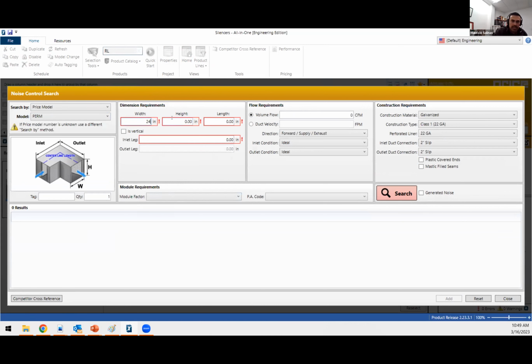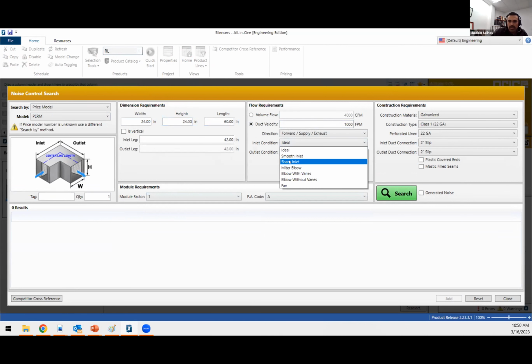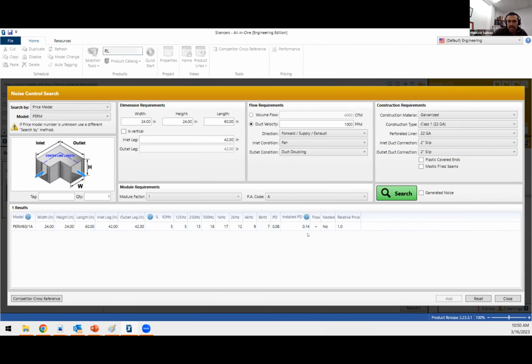So when you do that, let's say you select the silencer and you know that you want a 1A with 1,000 feet per minute. And then you know kind of what to expect. Sharp in, let's say you have a fan, and the duct is doubling, so transitioning, and that's the performance of a packless elbow. So as you could tell, the packless is going to perform less than something with media, right? So have that in mind.